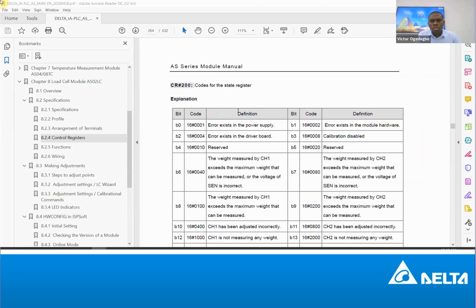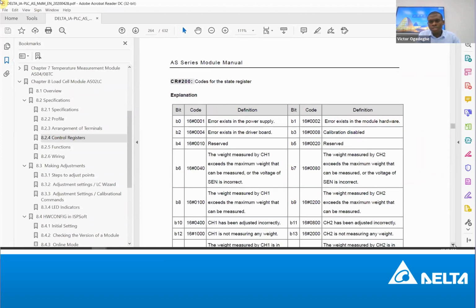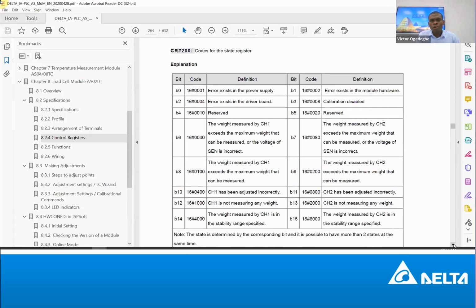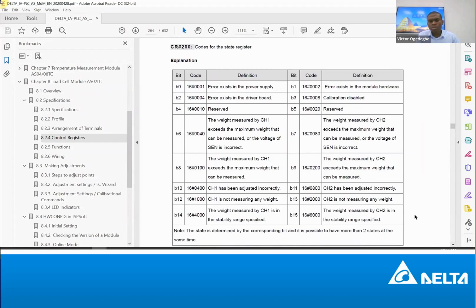Is up. So this status code is a 16-bit register. When there's an error on the load cell module, it gives you an indication of what the error could be. Bit 0 means that... power supply, there's an issue with the power supply, like bit 14, bit 12. So each bit has a meaning. So this status code, that is what you have here, status code.